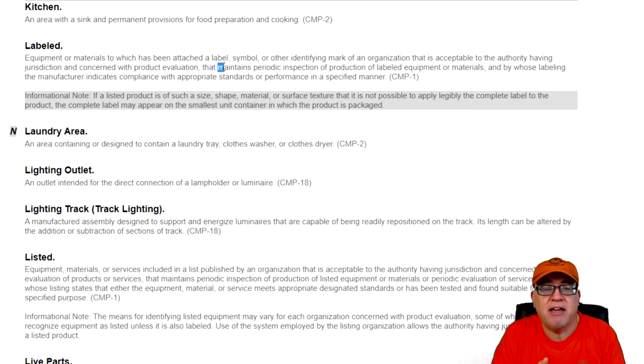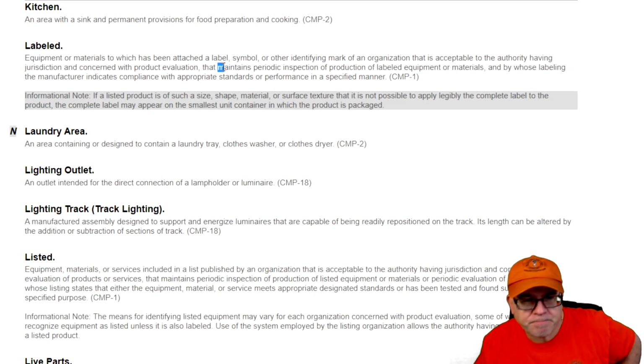Now you're going to have areas that are not kitchens. But the code now has said, look, we're going to give you other provisions for GFCI requirements. For example, if it acts like a kitchen, but it doesn't have the cooking in it or something like that, okay. But we're going to give you some rules for protection like GFCI and other things. We're going to say that it's acting close enough like a kitchen. But it's important that you know what a kitchen is because we have rules for kitchens that we have to be aware of in 210.52, okay, for receptacle spacing and placements and things like that, okay? All right.